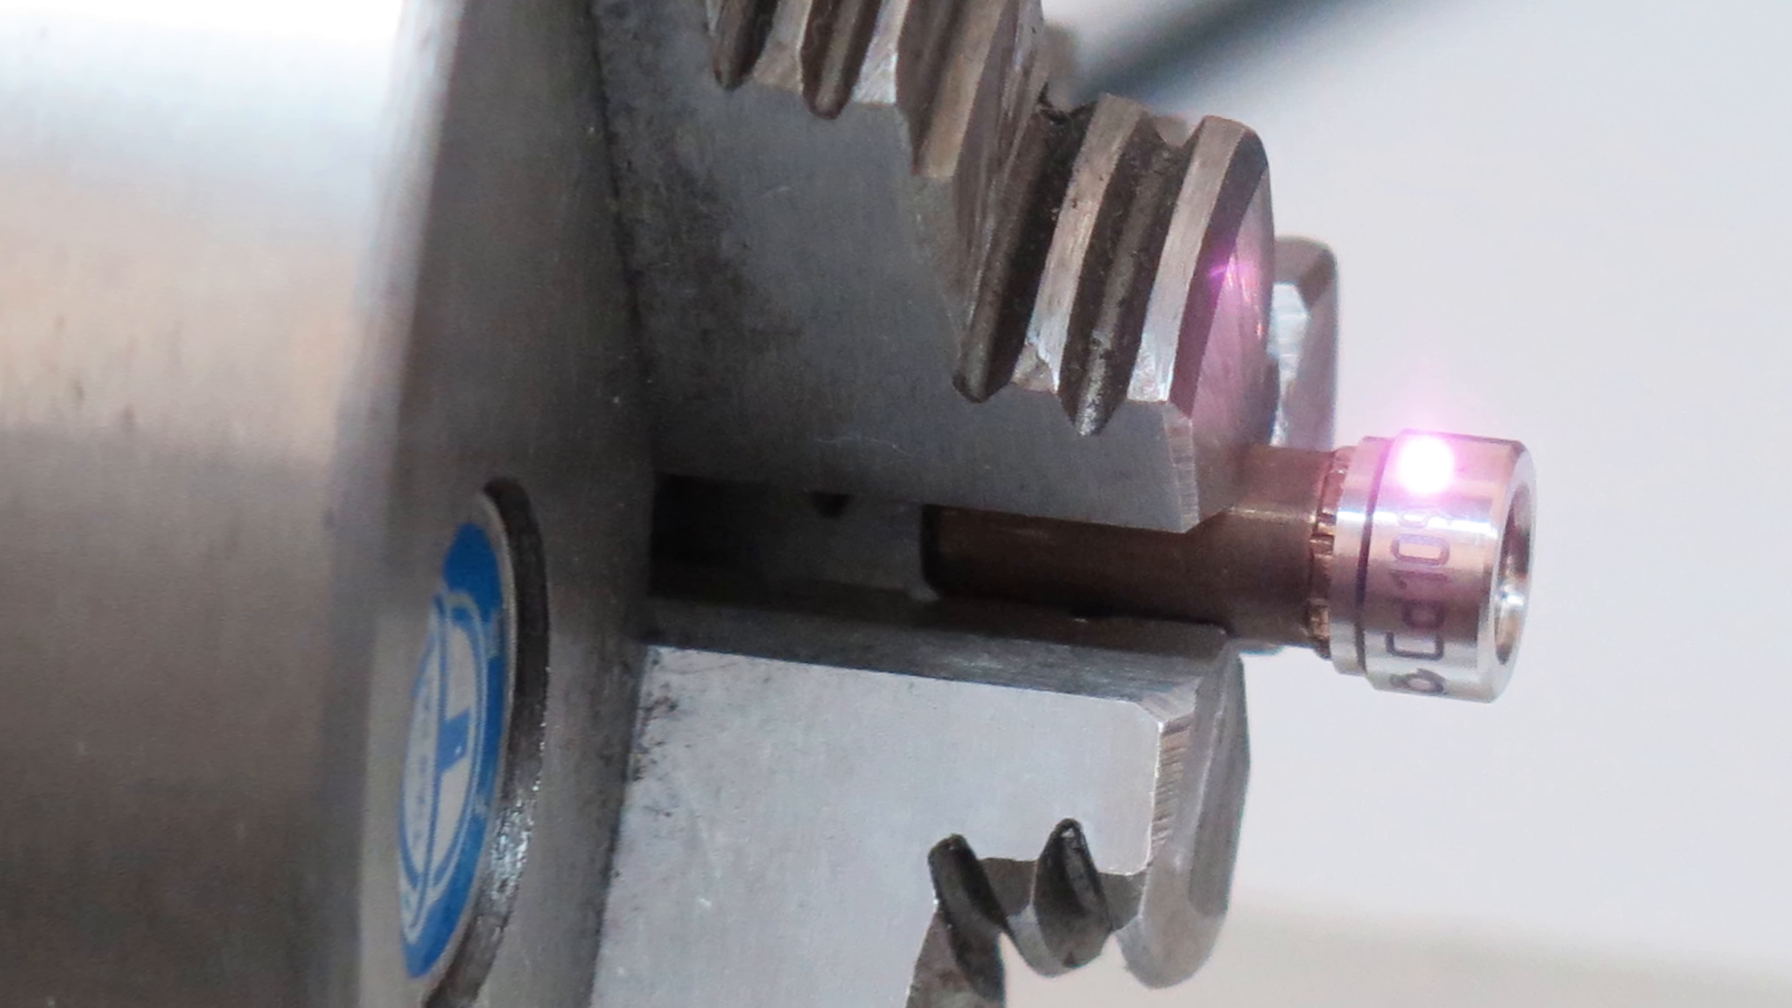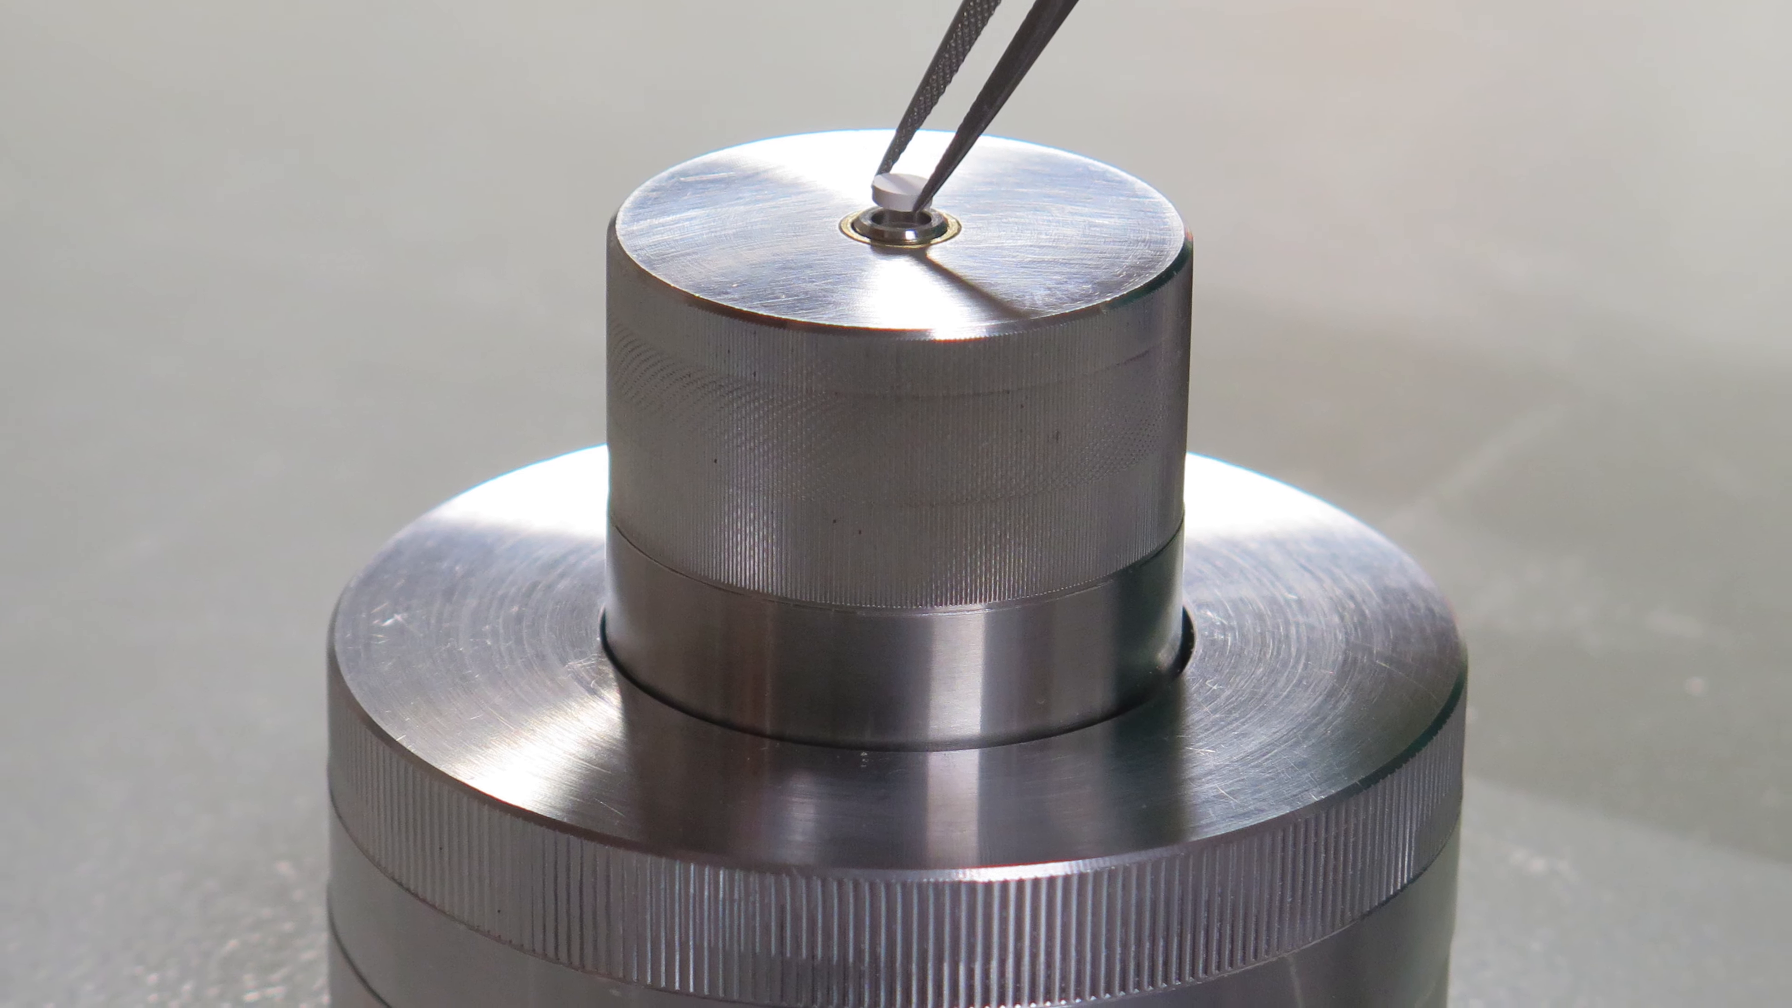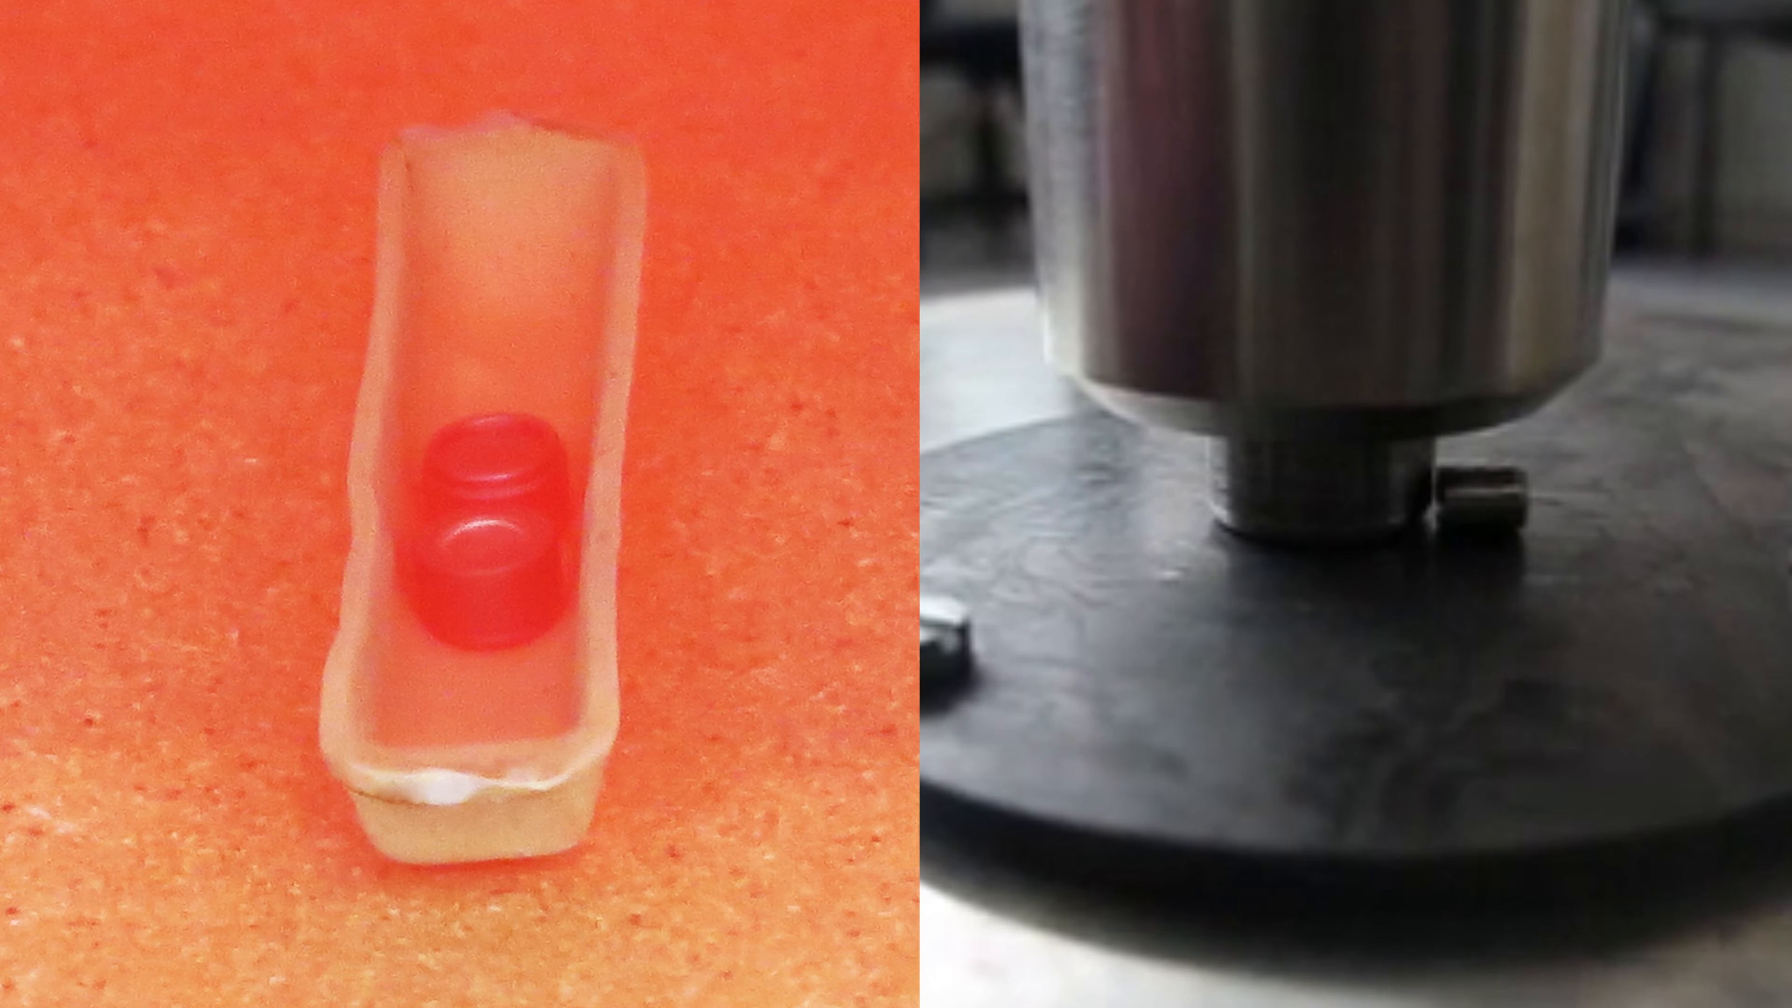A typical cadmium-109 sealed source is an active core containing a radioisotope placed into a metal capsule with an x-ray transparent window sealed airtight by welding. Capsules are usually very durable, being able to withstand environmental stress, including temperature and mechanical load.